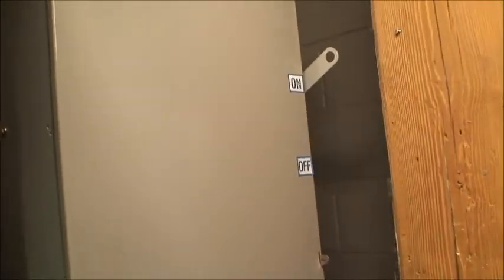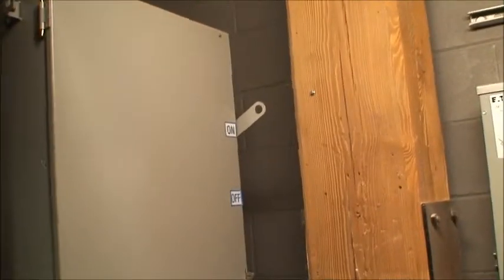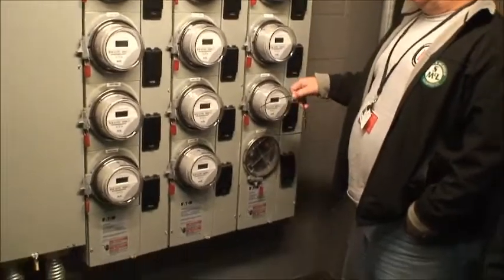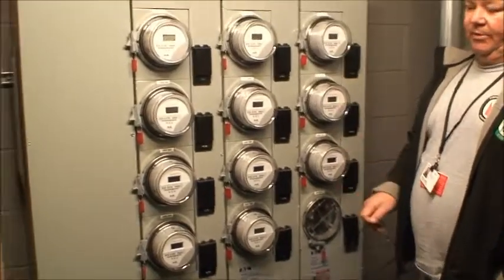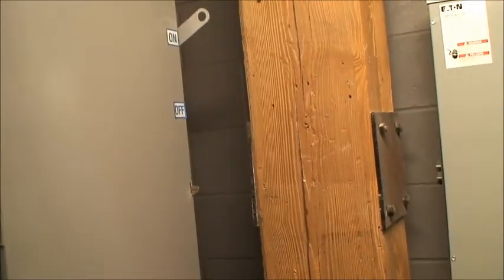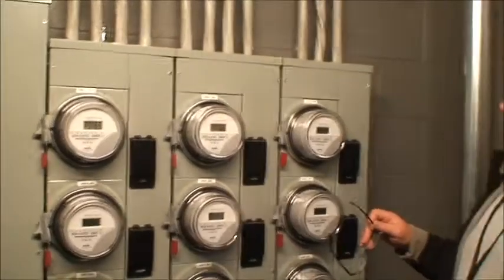Correct. The riser carries through the whole building. On each floor, you have a 600 amp disconnect. So if you need to shut off 4 or 5, it's a 600, but it's protected with 400 amp fuses. So it's really a 400 amp disconnect. It looks as big as a 600, but it's a 400 amp disconnect. If you needed to shut down power to work inside these meters, you can do it right there without having to affect other floors. So it's specific to each floor? Yes. You can shut down and work in here? Correct. Only shutting down right here to work though.